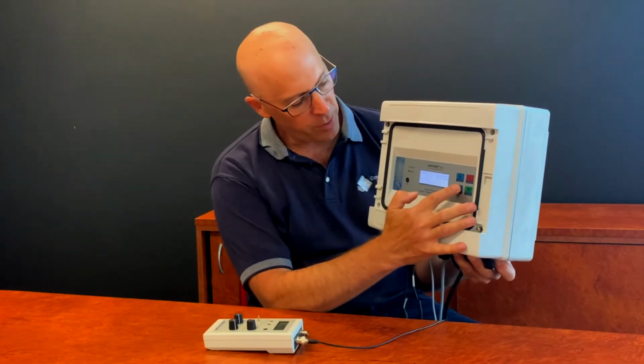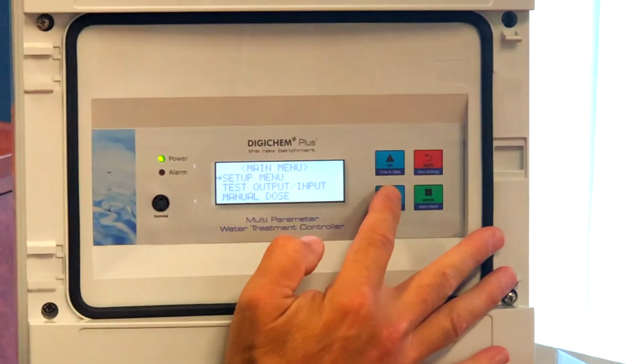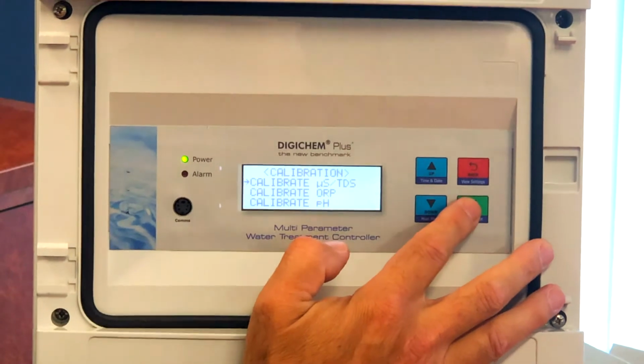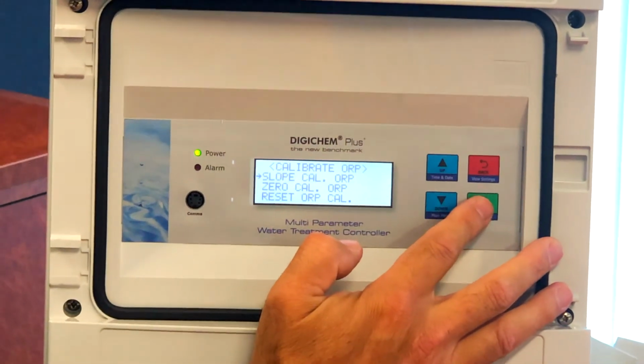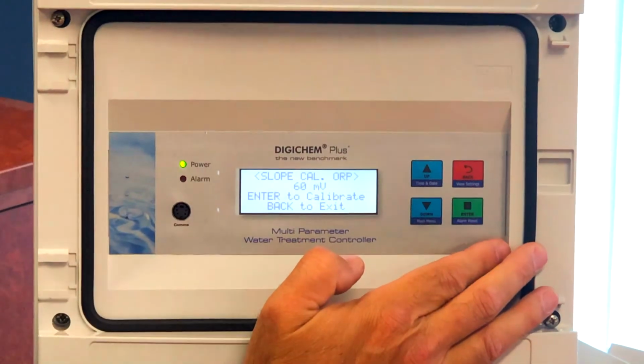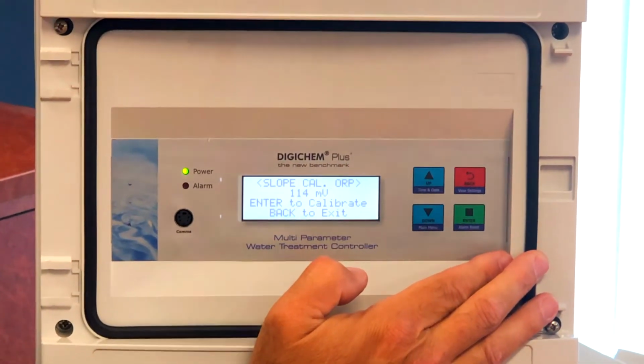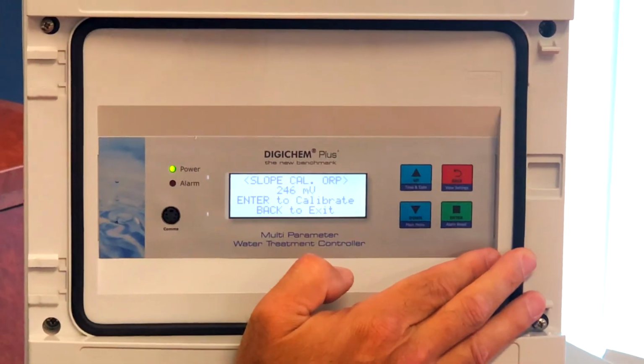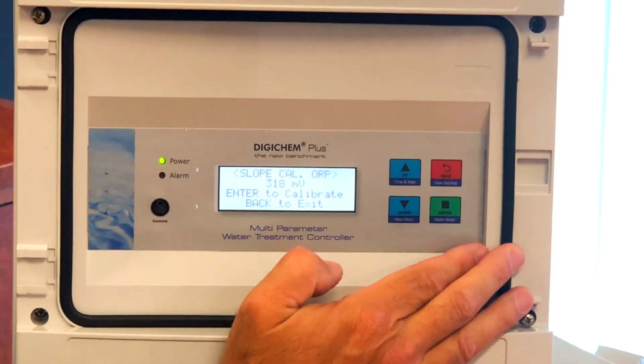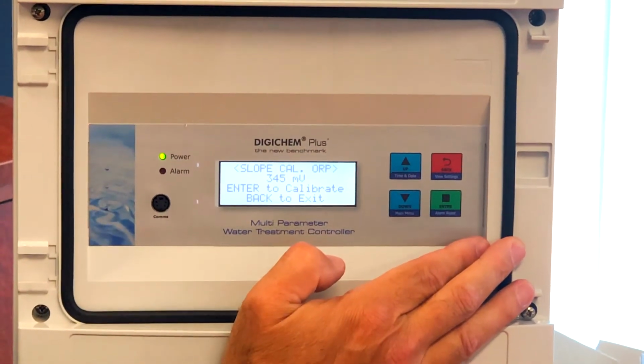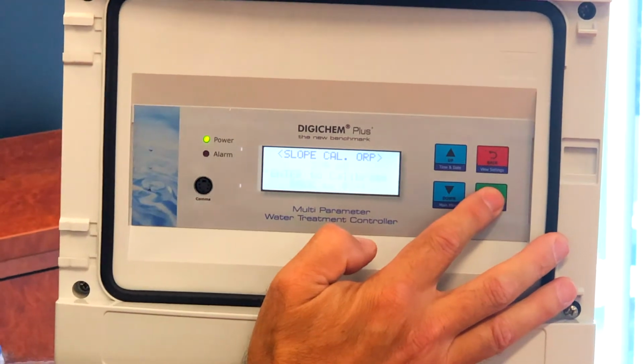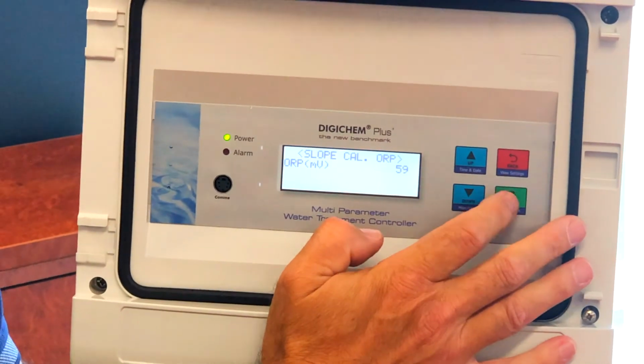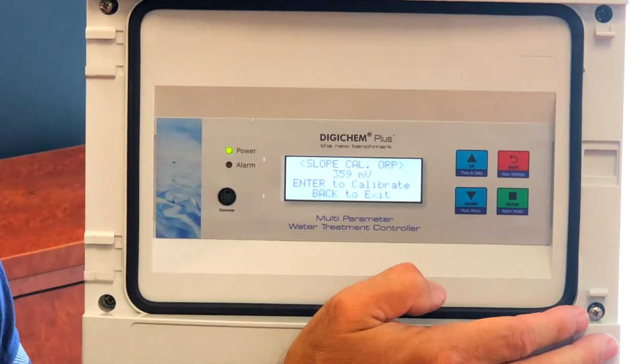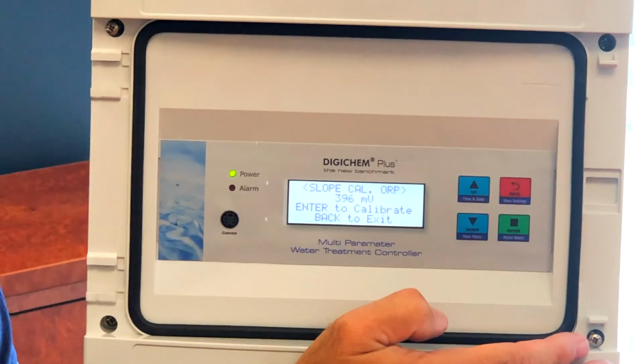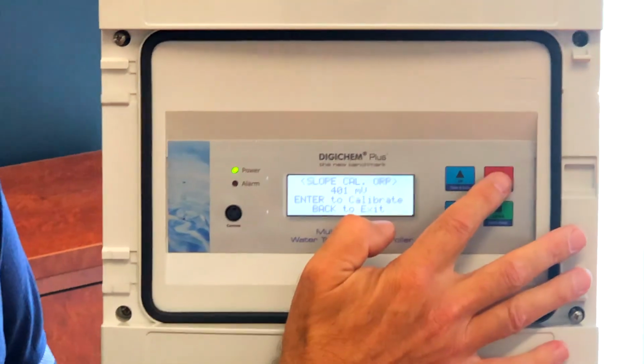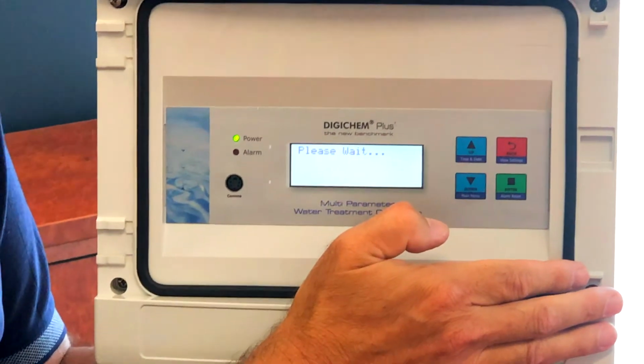We then go back into the calibration menu and we select ORP again. We now go to slope, so we press enter on slope, and now we wait for the value to rise up to 400 or thereabouts. When the value settles down, we then press enter, which will then enable us to change the value to 400, which is the value that we're calibrating it to. We press enter and we change the 359 to 400 and we press enter. And as you can see, the reading's now climbing up to 400. Once we're satisfied with that reading, we press the back button, and that means that the unit is now calibrated.